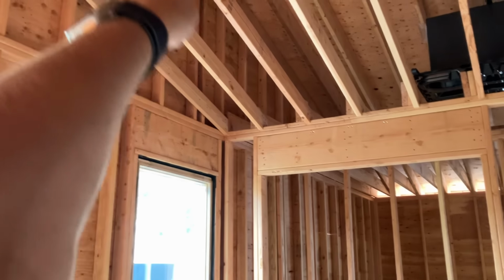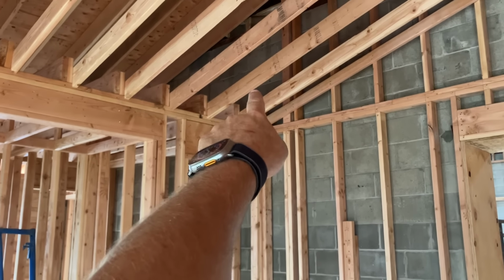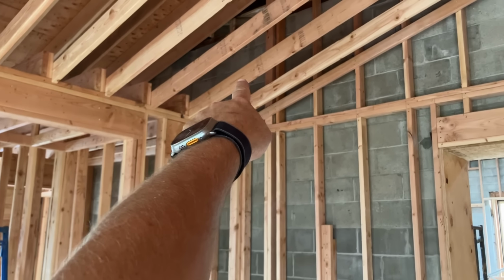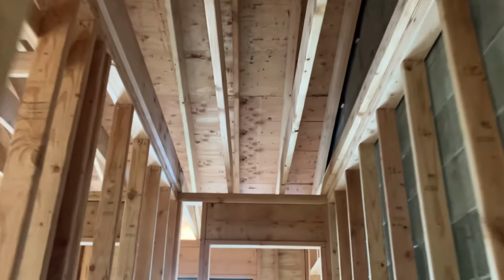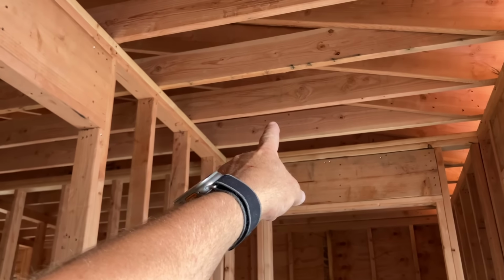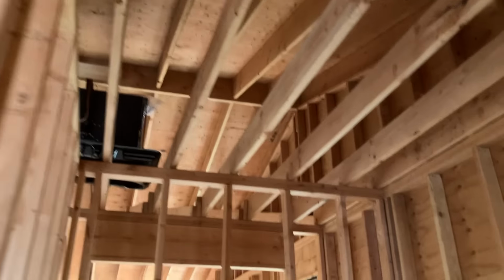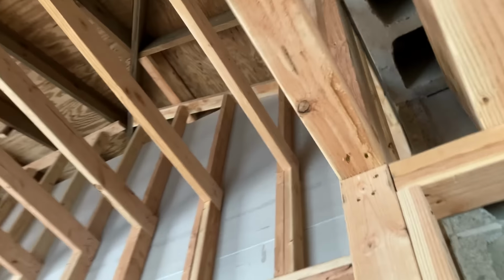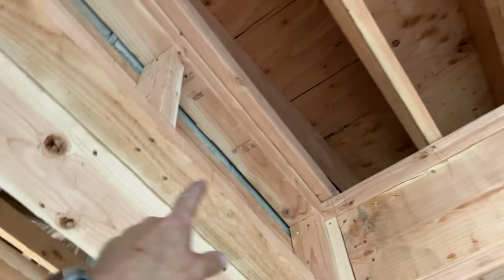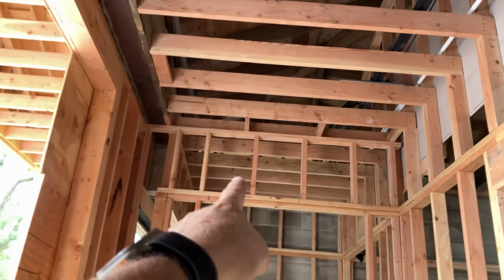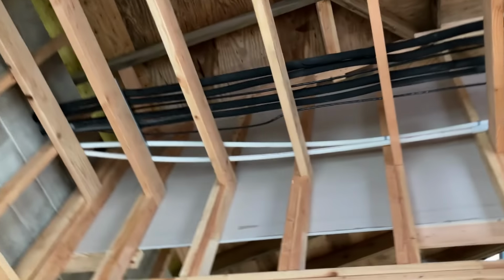We're going to put a 14 by 24 inch return right here. We're going to put a 10 by 10 by 7 side outlet return diffuser there, and there, running across. Here, we're gonna put a 14 by 24 return as well. We're gonna put a 10 by 10 by 7 diffuser and a 6 by 6 by 5 in this large bathroom. This closet's not gonna get anything. And then once our contractor builds this out, and busts through this cinder block wall, we're gonna bring one more duct up and across all the way to this room right here. And this is gonna be the, I guess, receptionist room. So she's gonna have a duct right there. But there it all is.